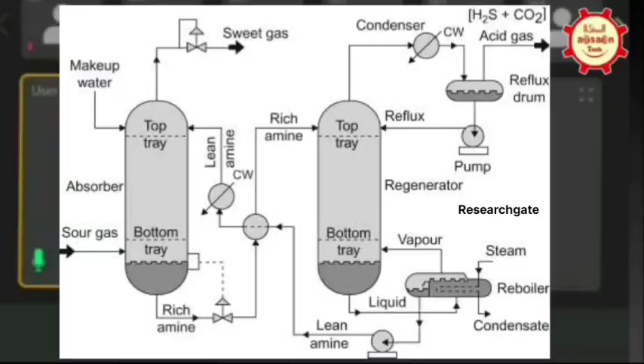Yes, so PWHT, mostly it will become mandatory. If it is amine, we can say like that. Sometimes I have seen two types of design. One is downstream of the flash drum, there will be a pump. After the pump itself, they start SS metallurgy. But some Indian clients go for cost, so they will go SS only after the valve upstream of the regenerator, which is where the flashing happens. That's a letdown valve, so only from there they will go for SS.